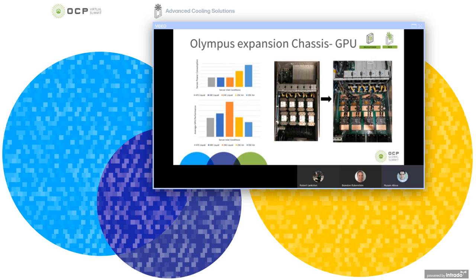This is another case study we ran on our Olympus expansion chassis, HGX1, which is a server with 8 GPUs. The air-cooled chassis was running using a 3U tall heatsink solution, while the liquid-cooled has been retrofitted with 8 cold plates. This study was a collaboration across the server, software, hardware, and GPU teams, as well as externally with CoolIT, ZT Systems, and Ingrasys.